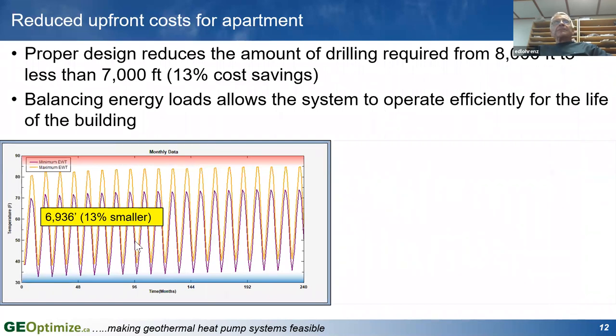Whereas the apartment building, because the amount of energy that you're pushing into the ground and pulling from it is fairly balanced, it's going to run happily forever, well within the operating range. And at the same time, at 7,000 feet of drilling, not the 8,000 feet that the rules of thumb would suggest. So this one would be less expensive than rules of thumb would suggest. The other two wouldn't work very well.